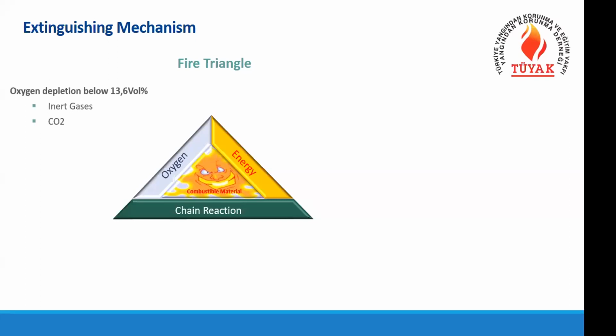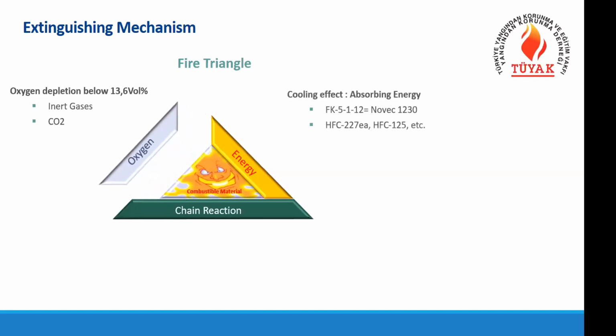And this fire triangle is also used for the fire extinguishing mechanisms. One of these items will be critical for us to define our fire protection system. So when we use inert gas like argon, nitrogen, or their mixes, or CO2, we are trying to reduce the oxygen volume, the oxygen rate inside the room or area, below 13.6%. So when this happens, we don't have enough oxygen for the chemical reaction of fire. So we can avoid fire, or after the fire starts, we can stop the fire by reducing the oxygen.